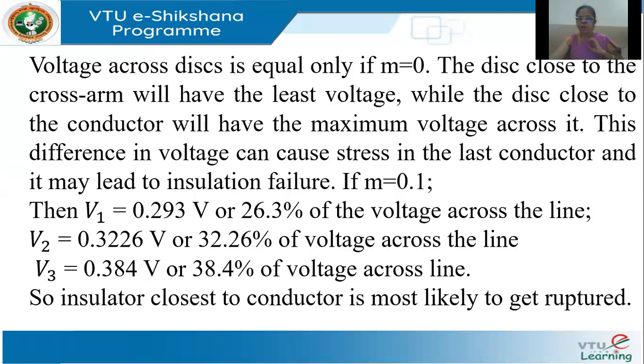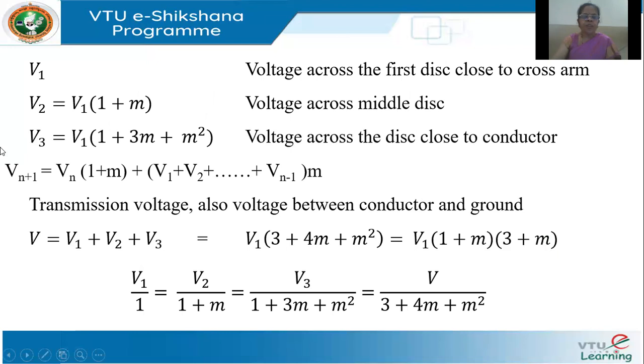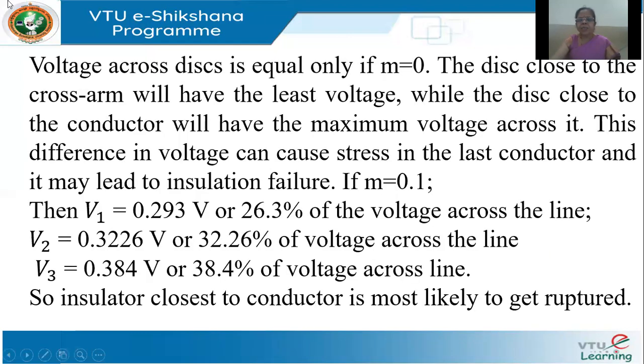When will all these voltages be equal? V2 equals V1 only when m = 0. Similarly, V3 equals V1 only when m = 0. But m = 0 means there is no shunt capacitance, which is not possible — the shunt capacitance is always present. The shunt capacitance is normally around 10 to 15 percent of the self-capacitance, meaning m is around 0.1 to 0.15 generally.